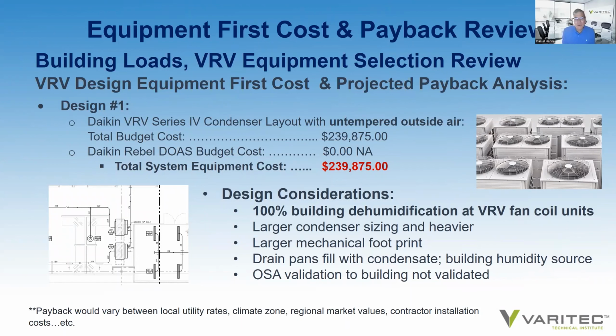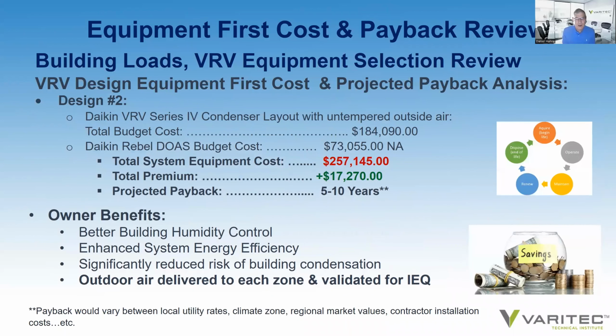If we look at design number 2, we see that the system, including the DOAS unit and the VRV, is more money. It's $17,270 more to purchase the VRV and the DOAS equipment than it would be for the untempered system. However, we see a projected payback for a 28,000 square foot medical office building of 5 to 10 years. And since variable refrigerant systems are designed to last 20 years, not the 10 to 15 years that current package DX units are built for, then if we look at the life cycle cost of the VRV system, there are some pretty compelling reasons why you might consider this first cost premium.